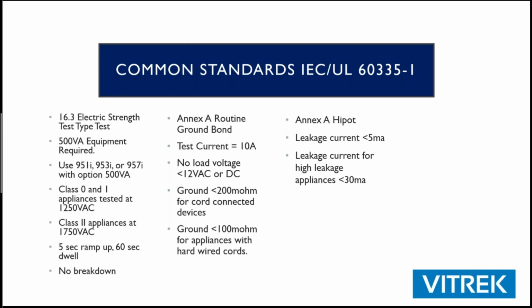The majority of these products are going to be tested at under 2,000 volts. All of our testers do that. You're going to have dwell times anywhere from 1 second to 60 seconds, and then ground bond up to 40 amps. Typically, you're going to be limited to about 150 milliohms of resistance in between that earth ground pin and chassis in a class 1 device.